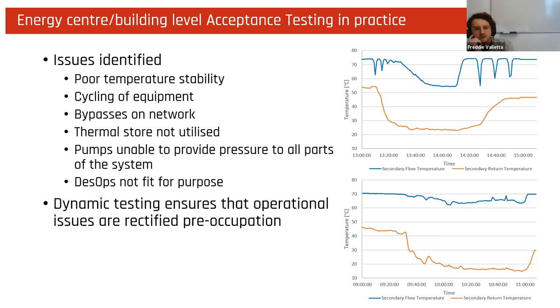With an example on the right-hand side here, these are two iterative tests over 2 days. And these are secondary flow temperature and return temperature on the secondary side of a district heating plate heat exchanger. In the load test on the first one, once this load was induced, the return temperature was dropping as we would expect as demand was induced on the system. However, the secondary flow temperature also dropped drastically during this period. And then once this load was removed, the plate control caused several fluctuations in that return temperature, as can be seen in the dips in the blue line in the top right-hand corner.